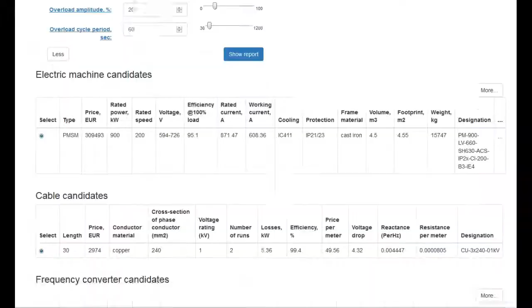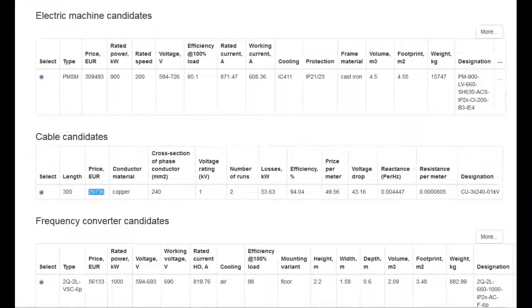But what if we need a longer cable if we want to drive the motor from the distant powerhouse? So what happens to the cable now? We see the efficiency is quite reduced. It is 94% instead of 99%, and the cable gets quite expensive. It is 29,000 because copper is expensive and the installation is expensive.